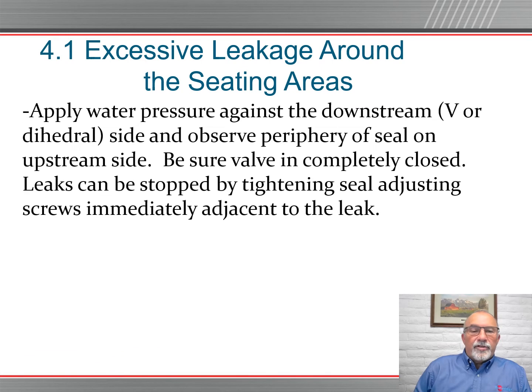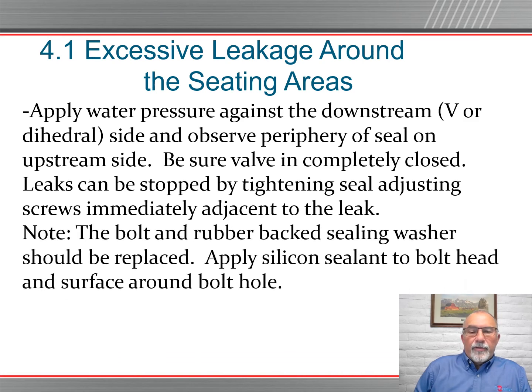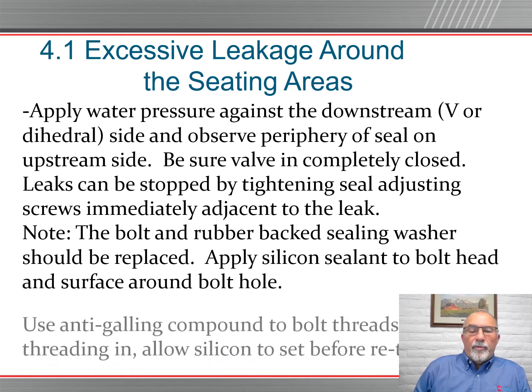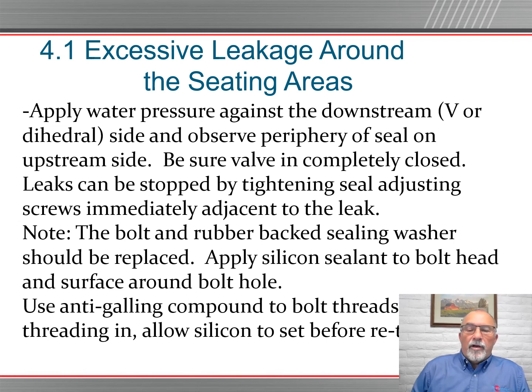If you have excessive leakage around the seating areas, apply water pressure against the downstream side and observe the peripheral seal on the upstream side. Be sure the valve is completely closed. Leaks can be stopped by tightening the seal adjustment screws immediately adjacent to the leak, as discussed earlier. The bolt and rubber back sealing washers should be replaced. Apply silicone sealant to the bolt head and surface around the bolt hole. Use anti-galling compound on bolt threads and nuts throughout. After threading in, allow silicone to set before retesting.